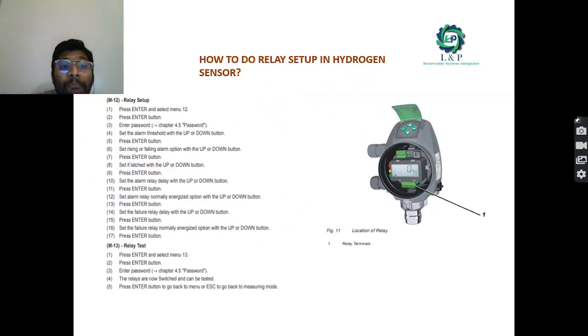And if you go for menu 12, that is relay setup. Enter the menu, press menu 12, press enter and use the default password 0000. Using the alarm, if you want to change the threshold value, you can change it using the upward and downward buttons. You can set the rising or falling alarm option with the up or down button and press enter. Whenever choosing anything, please press the enter button, then only the option will get selected, okay.